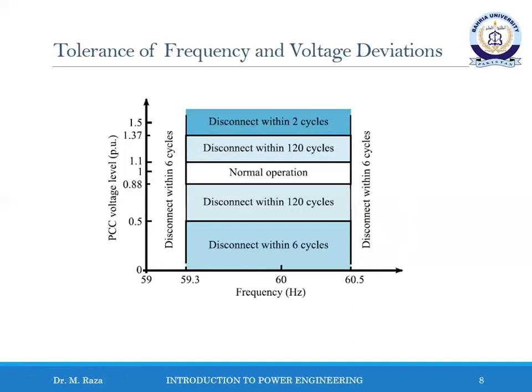Further, if PCC bus voltage fall in the range of 1.1 to 1.37 per unit or 0.88 to 0.5 per unit, then PV system must be disconnected from the network within 120 cycles, such as this region. And if the voltage drop below 0.5 per unit, then it must be disconnected within 6 cycles. And if the voltage rise above 1.37 per unit, then it must be disconnected within 2 cycles.